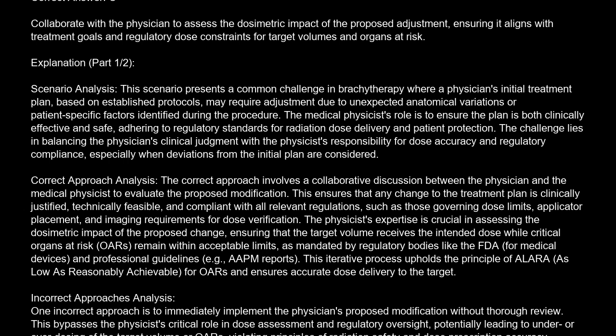Correct approach analysis. The correct approach involves a collaborative discussion between the physician and the medical physicist to evaluate the proposed modification. This ensures that any change to the treatment plan is clinically justified, technically feasible, and compliant with all relevant regulations, such as those governing dose limits, applicator placement, and imaging requirements for dose verification. The physicist's expertise is crucial in assessing the dosimetric impact of the proposed change, ensuring that the target volume receives the intended dose while critical organs at risk remain within acceptable limits, as mandated by regulatory bodies like the FDA for medical devices and professional guidelines, e.g., AAPM reports. This iterative process upholds the principle of ALARA, as low as reasonably achievable, for OARs and ensures accurate dose delivery to the target.